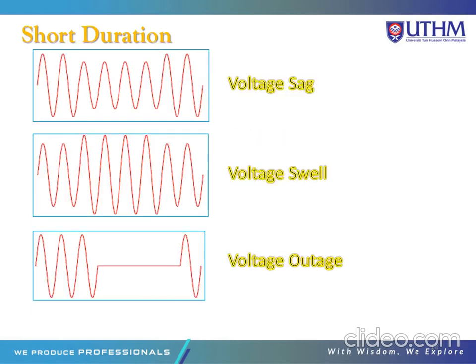For short duration there are three types of PQ problem. The first one is voltage sag. We can see here the sagging of the voltage, the voltage drops for a certain short duration. For voltage swell, the voltage is increased or overshoots. We can see here overvoltage for a certain short duration. And then we have voltage outage here, where the value is zero for a certain short duration.